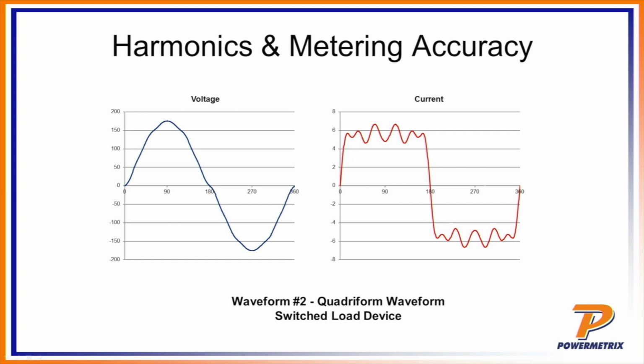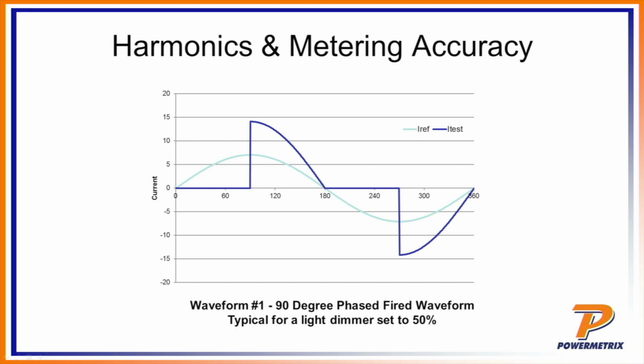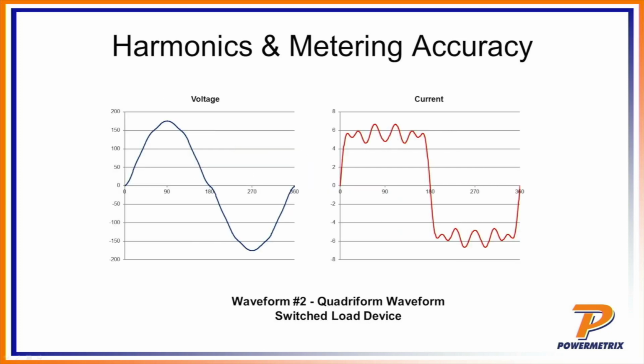Electromechanical meters, historically, were designed to measure 60 hertz, the fundamental. Some other companies have done tests on those electromechanical meters and have found that most start to peter out at about the 7th or 8th harmonic. So if I've got a waveform like the phase-fired waveform or this quadriform, with harmonics up into the 10s and 20s, solid-state meters do a really good job. Electromechanical meters, not nearly so much. They start to lose a lot of that high-end energy.